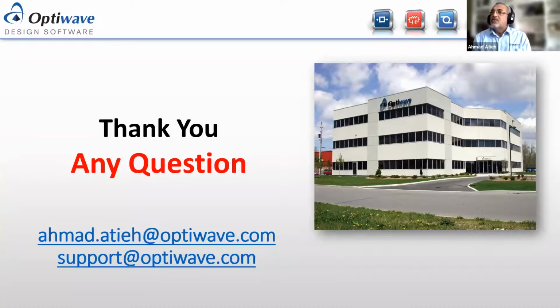Another question is, does OptiInstrument support the automation of multiple equipment from different vendors? As we talked about, OptiInstrument is not dedicated to a specific vendor. We can work with any equipment and any vendor that supports SCPI commands or serial commands, or, for example, commands added through custom Python files, as we showed you today. So OptiInstrument is a versatile software which can talk to any equipment.